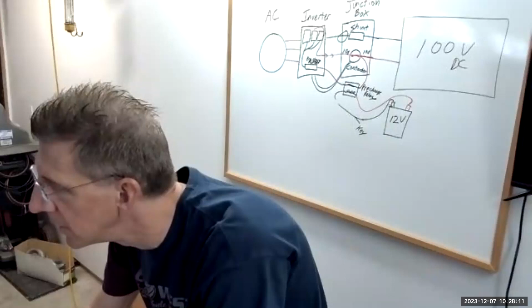So yes, there are different ways of testing insulation, and so you have an insulation tester. Generally, we're using those for measuring the windings of the motor, and to see if the electricity is leaking from the windings to the case. So that's going to be an insulation tester. You're not using that for checking an isolation fault. You're just using that, once you've determined that the fault is coming from the motor, to verify that it is indeed in the motor. So you could disconnect the motor, and if the voltage test that I showed you quits happening and the voltage drops like it's supposed to, then you can say, okay, the problem's in the motor. Then you're going to use your insulation tester to see if it's in fact the windings leaking to the case.